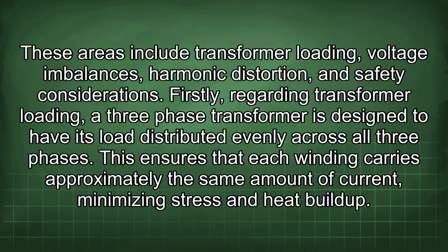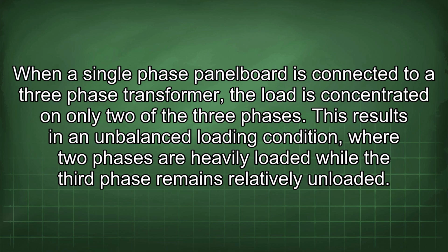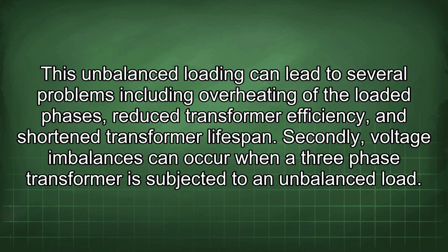Firstly, regarding transformer loading, a 3-phase transformer is designed to have its load distributed evenly across all 3 phases. This ensures that each winding carries approximately the same amount of current, minimizing stress and heat buildup. When a single-phase panel board is connected to a 3-phase transformer, the load is concentrated on only 2 of the 3 phases. This results in an unbalanced loading condition where 2 phases are heavily loaded while the 3rd phase remains relatively unloaded. This unbalanced loading can lead to several problems, including overheating of the loaded phases, reduced transformer efficiency, and shortened transformer lifespan.